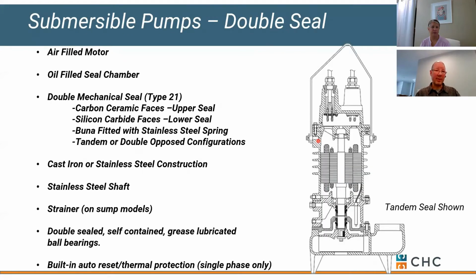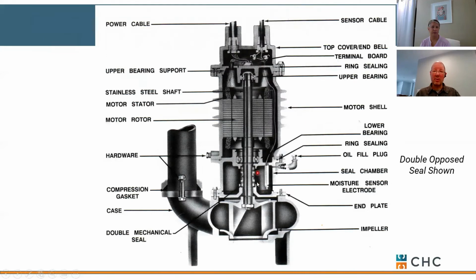Most of our commercial applications use something we call double seal. And again, that's 2 seals that are working together. Now there's 2 ways to condition those. One is to have one of the seals in the oil bath, and the other seal is in the fluid that is being pumped. So this works fine for groundwater or rainwater runoff. May not be the best for sewage. If you've got some nasties in your water, we may want to protect both seals and have them run in a cleaner environment, which is an oil bath. So this is not a heavy adder. I think it's a $50 adder to put both seals in an oil bath versus one in the fluid being pumped. Okay, but you could order a pump both ways.